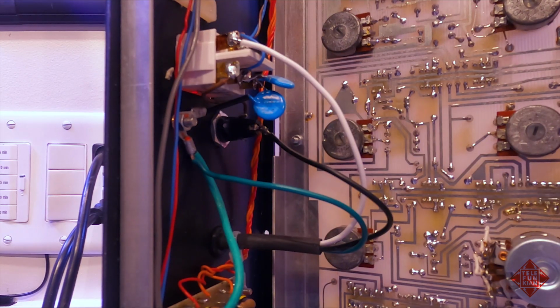Another thing I wanted to mention was the incorporation of safety capacitors, X and Y rated safety capacitors, both across the live and neutral, and from the live to ground. This is meant to be an RF noise suppression approach.